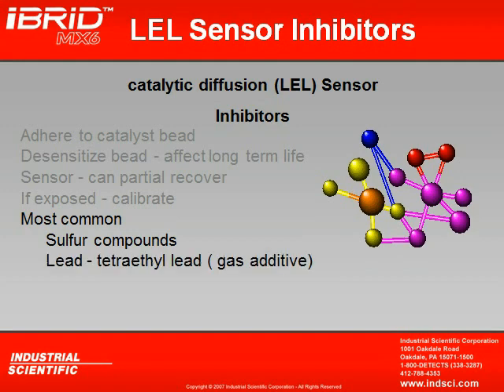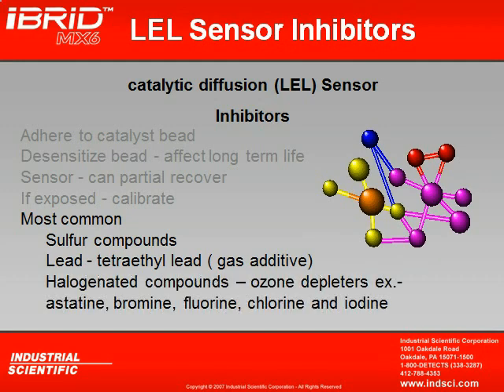We also have to watch out for leaded compounds like you find in leaded gasoline. But we also have to be concerned with halogenated compounds. Now, halogenated compounds are any type of ozone-depleting type gas, which then becomes very important as to what you choose to clean your instrument with. Because some people will actually use some sort of cleaning agent that has a propellant in it that is a halogenated compound. Well, the best thing to use to clean the outside of the instrument is mild soap and water. That's what our repair department uses. They use 1 part Dawn dishwashing detergent to 10 parts water, and it seems to cut through the grease the best. So we don't want to use any harsh chemicals on the outside of the instrument when we clean it. We want to stick with mild soap and water.